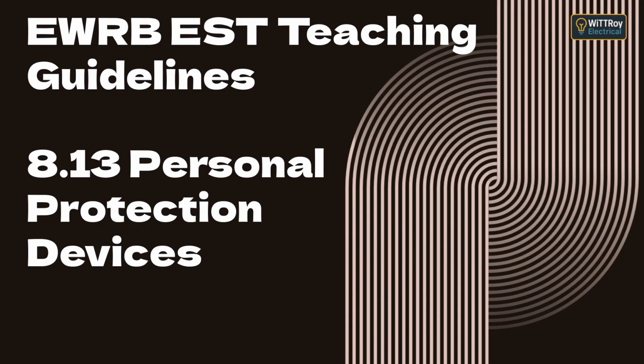Topic J. Basic principle of isolating transformers. Now let's move briefly to isolating transformers, which also provide personal protection but in a different way. An isolating transformer has separate primary and secondary windings with no direct electrical connection between them. This isolation prevents a user from receiving a shock because there's no return path to earth from the secondary side. Topic K. Safe use and earthing. Maximum safety is achieved when only one appliance is connected to the transformer's secondary. If multiple appliances are connected, their earth conductors must be bonded together at the transformer but not to earth, so there's still no path to earth through the body.